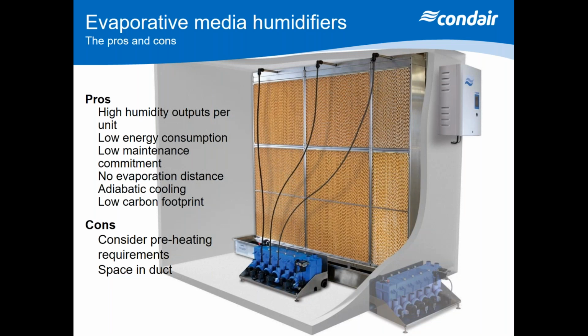Just to give you a rough guide, depending on hardness of water, in London, if you're working 24/7, it's not uncommon to have a cassette replacement every 3 to 5 years. Depending on the size, that can be quite a chunky cost, but it's something you need to program into your budgets if you are looking to have these in place over a 3 or 5 year period.